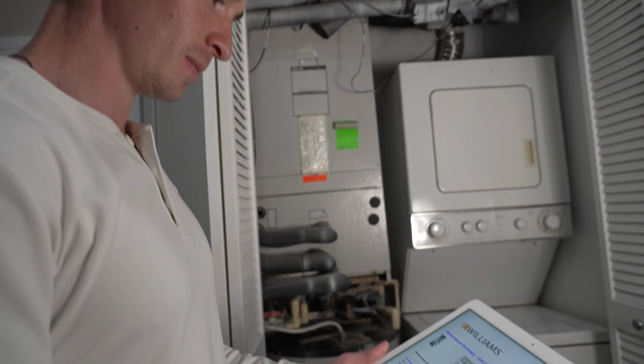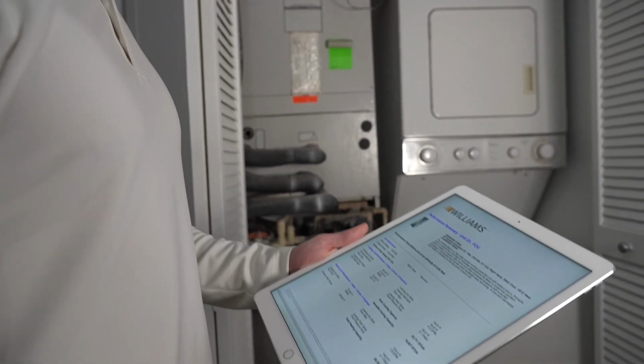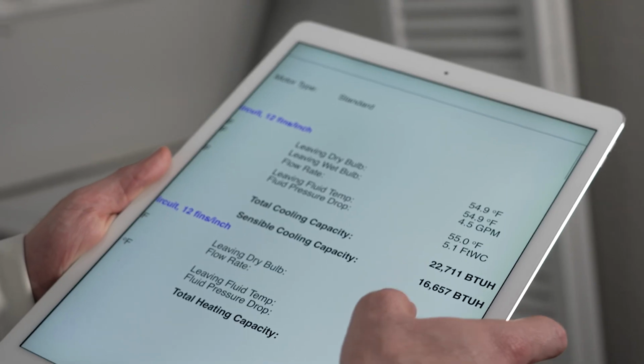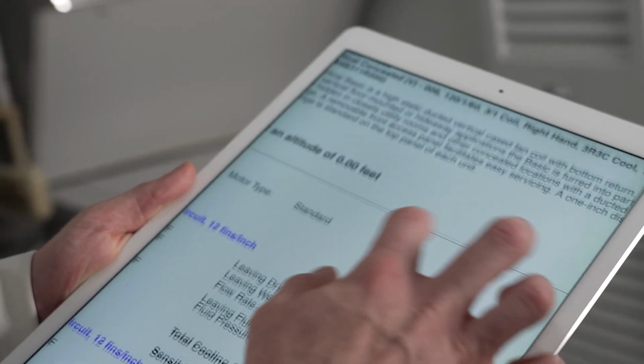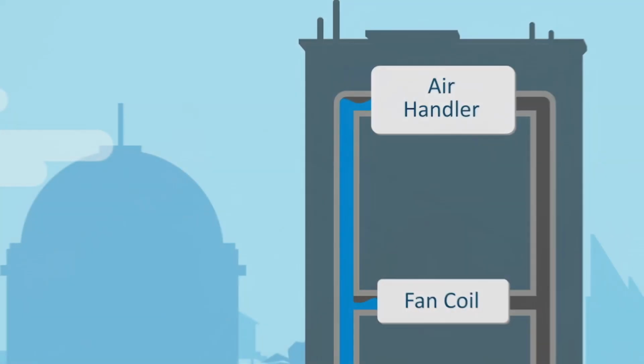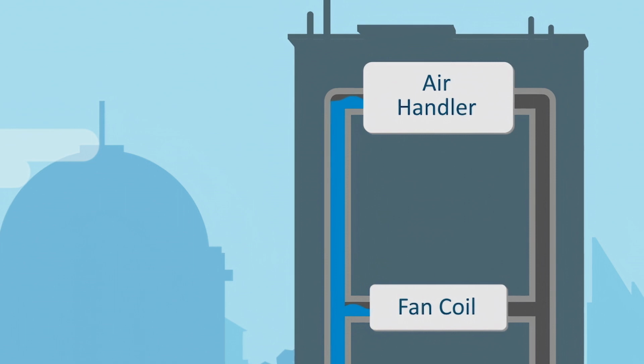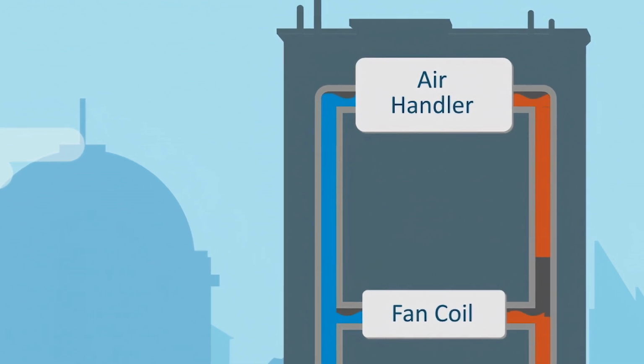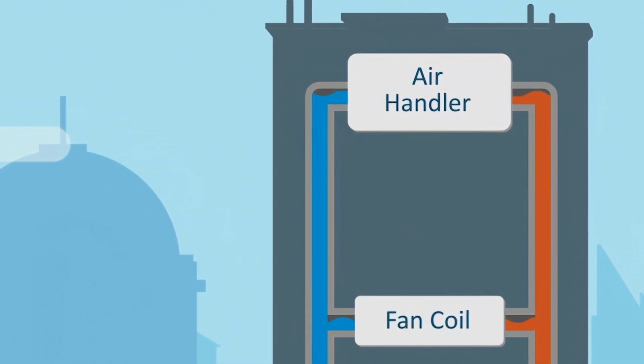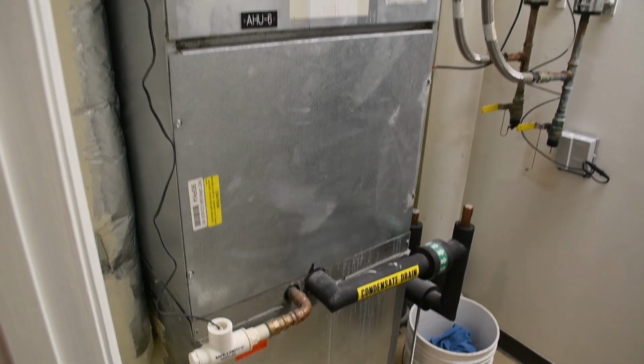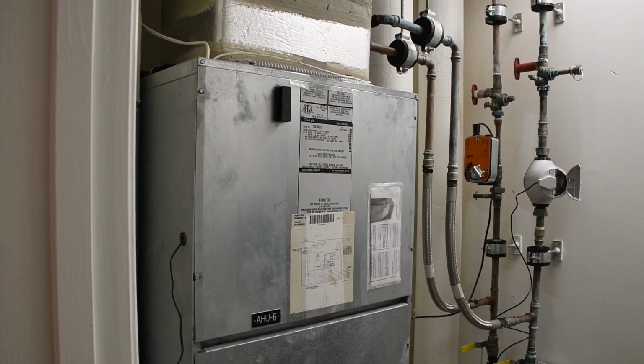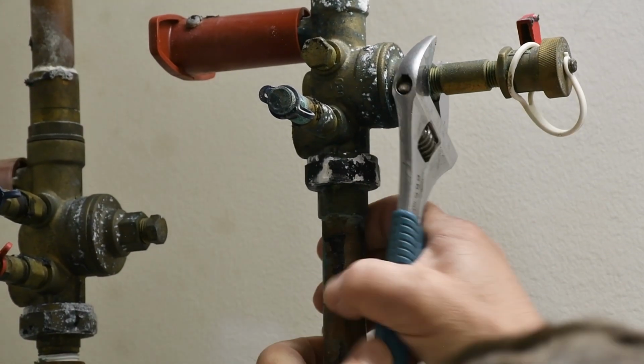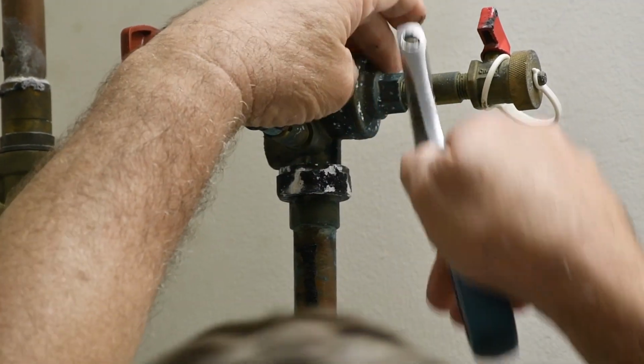Start by getting the factory specs of your system to understand how it should perform. You can get this information directly from the manufacturer or a local distributor. Here are the basics. A chilled water line supplies cold water to your fan coil, and a return line carries the warmed up water away from the coil. For each of these lines, there should be a small valve that allows you or a technician to isolate the fan coil to make repairs or perform maintenance.